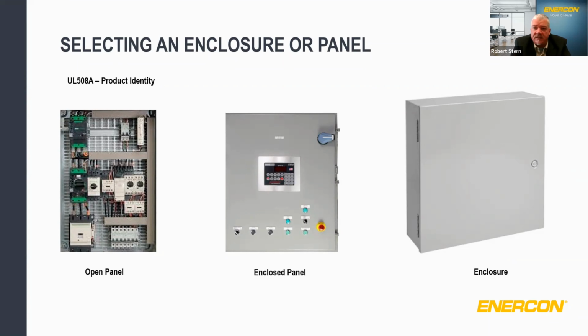So first off, you've got to decide what the platform is. Based on the application required, an industrial control panel with circuits and controls may be mounted on an open panel for mounting at another location or within an industrial machine. If it's an open panel, this is always considered to be a type 1 rating. A similar solution could be enclosed within a box as an enclosed industrial control panel, which could also be considered a type 1 rating. When the enclosure has been tested via UL 50 or UL 50E, additional ratings may be applied to the enclosure based on the features of the enclosure to withstand or prevent entry of dust, light, particulate, rain, sleet, ice, rust, oil, and non-corrosive fluids to varying degrees. Next slide.